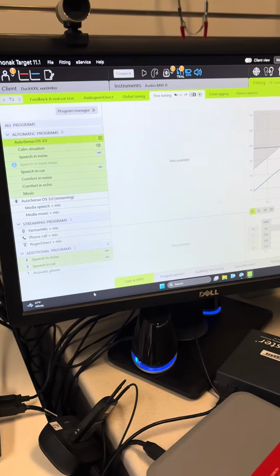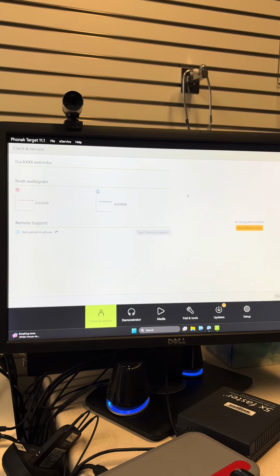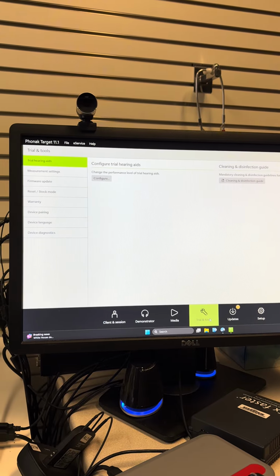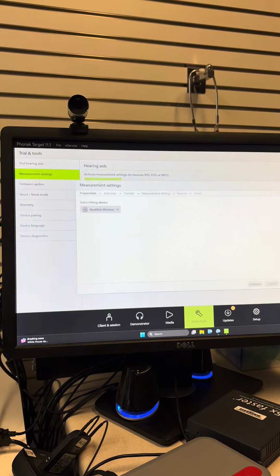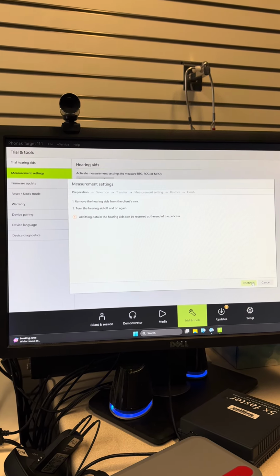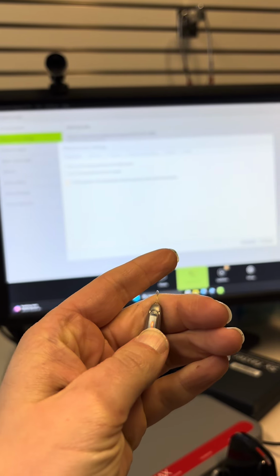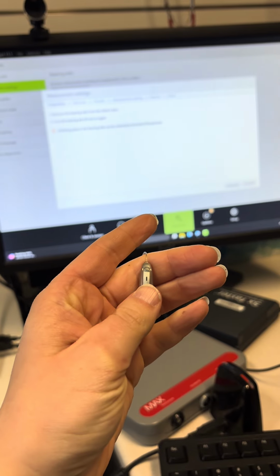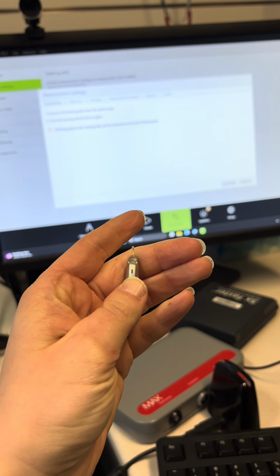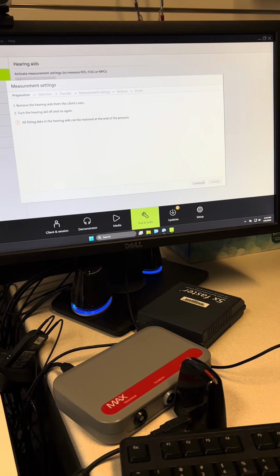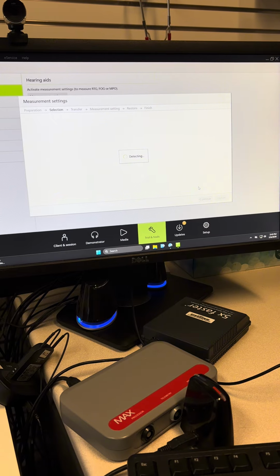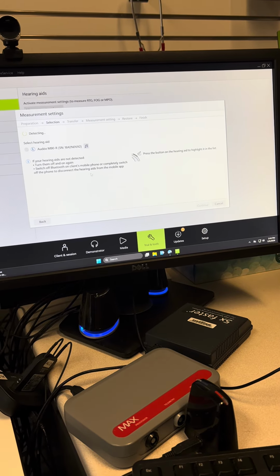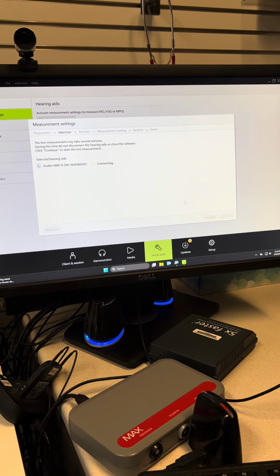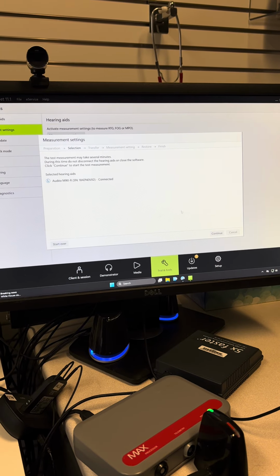Now we want to make sure that the hearing aid is set to full on gain. So here we opened up Phonak Target, and we are going to Trials and Tools, Measurement Settings, and we're using the Noah Link Wireless, continue, and we have to turn the hearing aid on and off again. Red means it's off. Then back on, and it should pick it up right here. We're only doing the left. Continue. Connected.